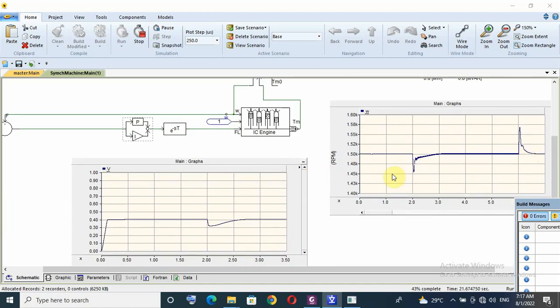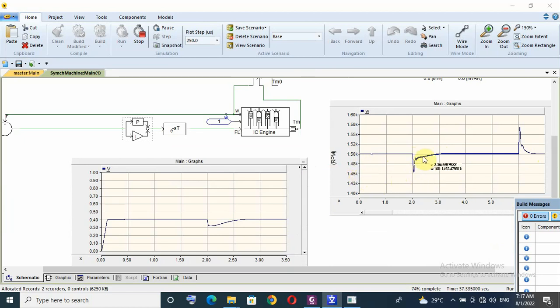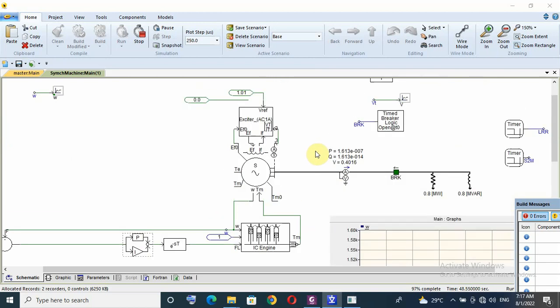I think now this response is okay because I apply full load so the speed decreases from 1500 or 50 hertz to 1450 and it recovers very fast less than one second. I see 0.5 second to normal value.